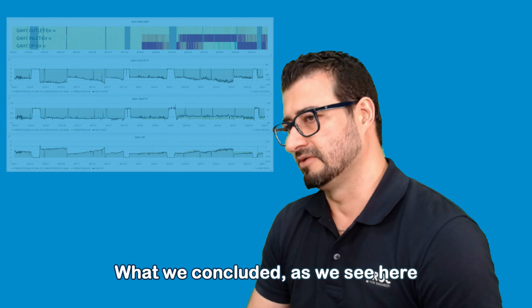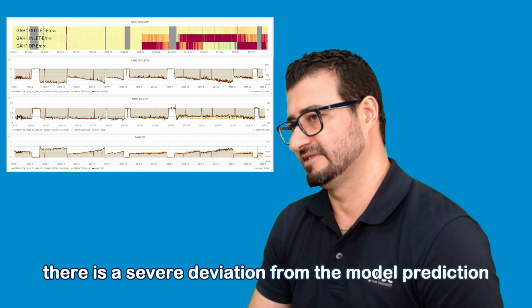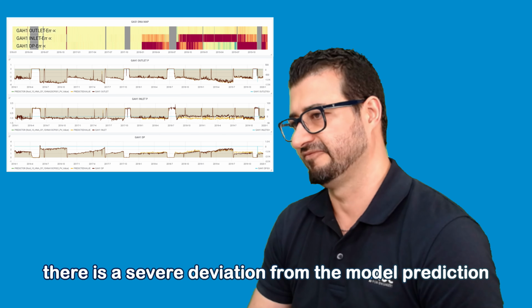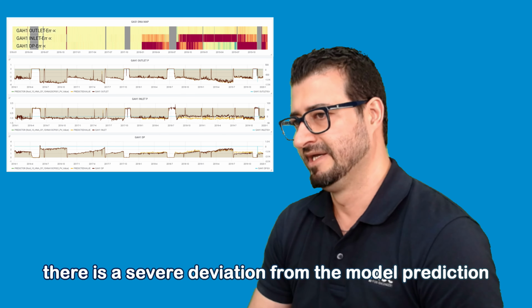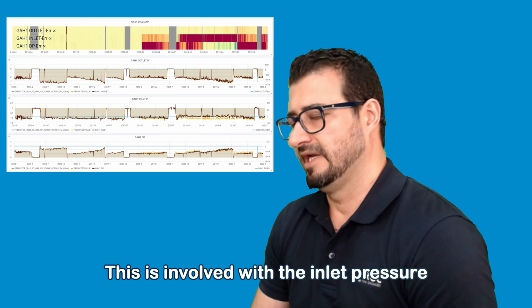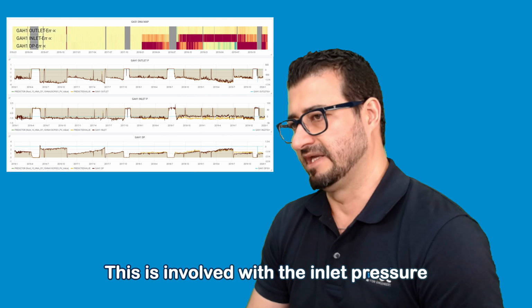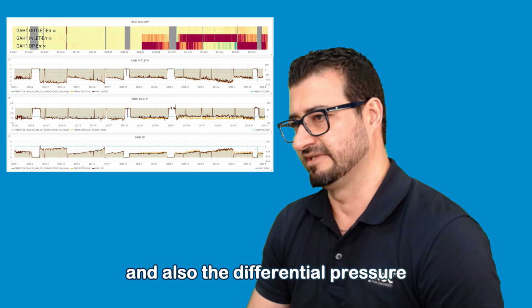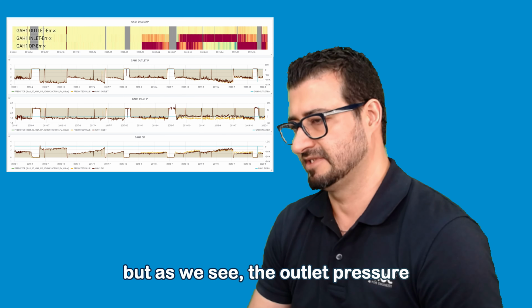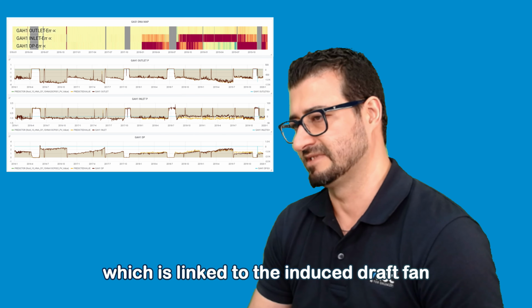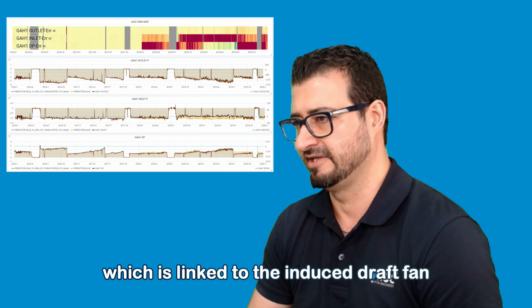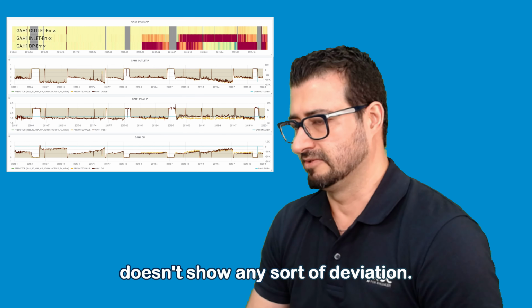What we concluded, as we see here, is that there is a severe deviation from the model prediction in the gas air heater. This is involved with the inlet pressure and also the differential pressure, but as we see, the outlet pressure, which is linked to the induced draft fan, doesn't show any sort of deviation.